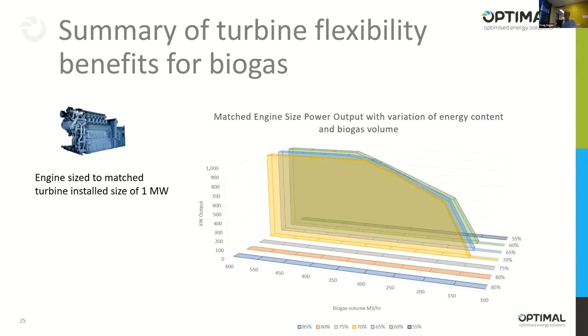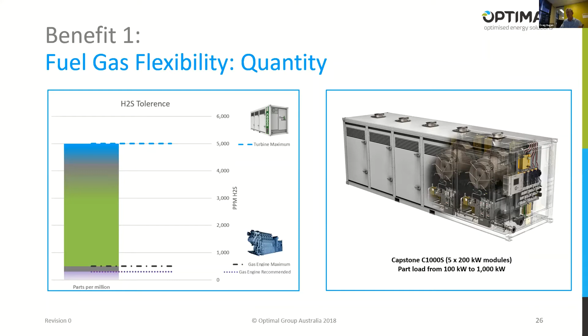The micro turbine, because it's made from exotic alloys, can run on very high H2S levels without any change to our setup - in fact, we'll run on 5,000 ppm H2S with zero removal of the H2S. Gas engines, if you do that, you have to be very careful with your exhaust systems. You would typically start them on clean natural gas and shut them down on clean natural gas, and then have to monitor corrosion very carefully.